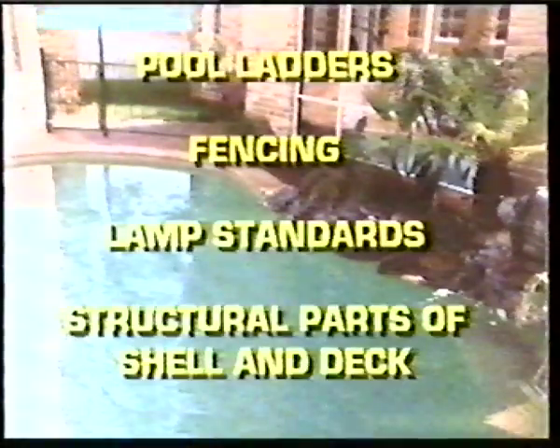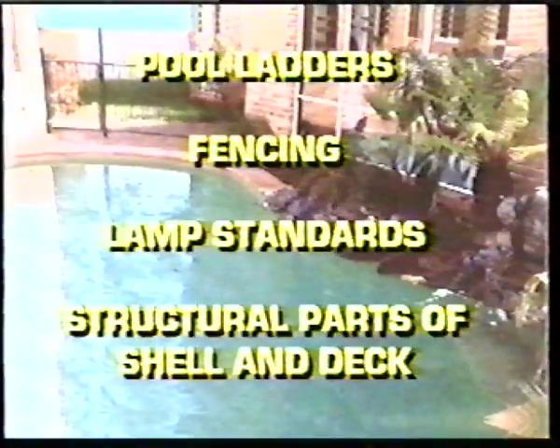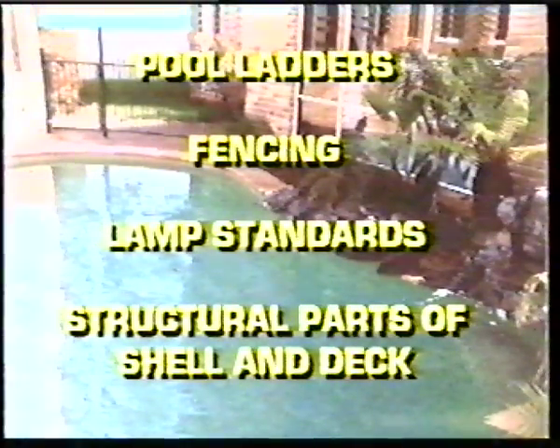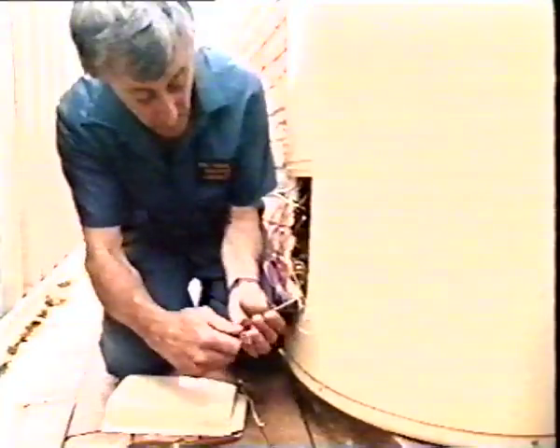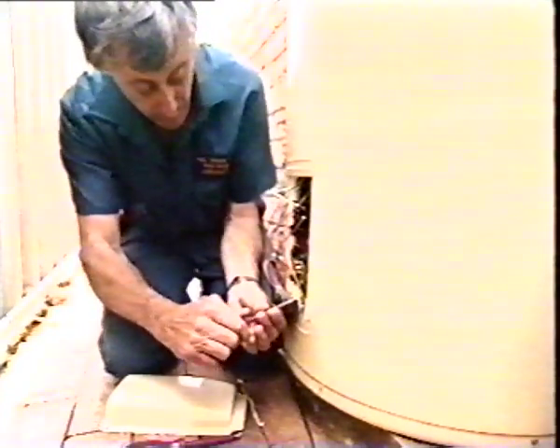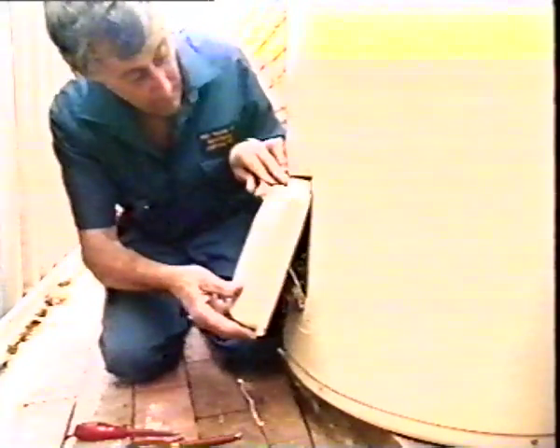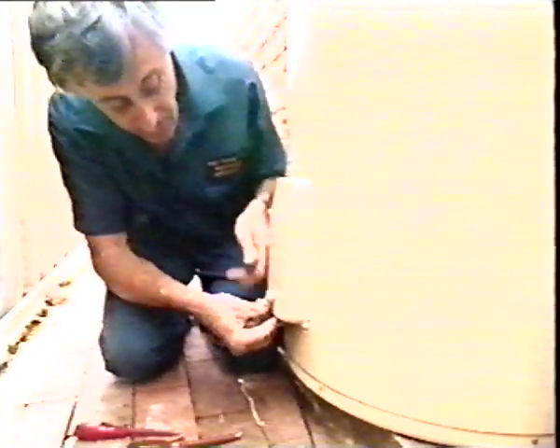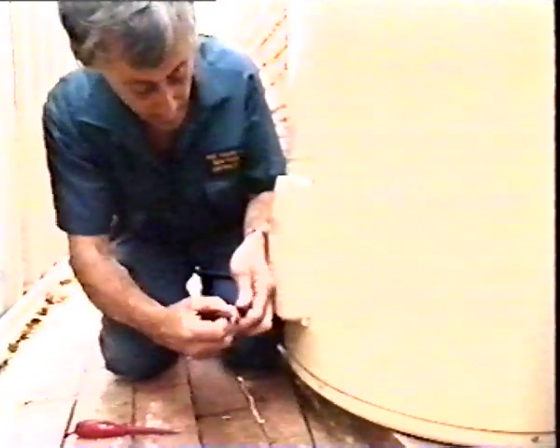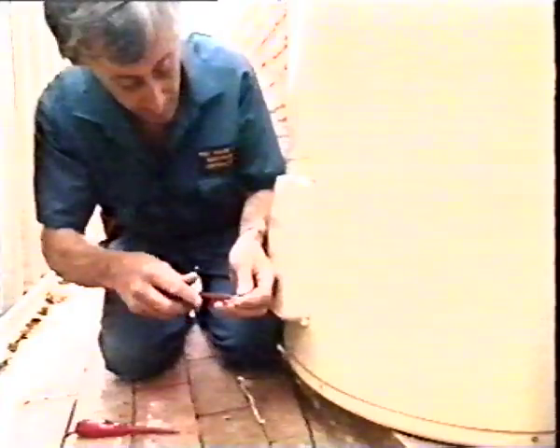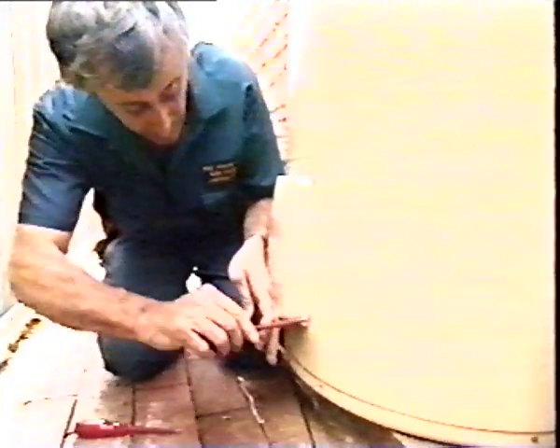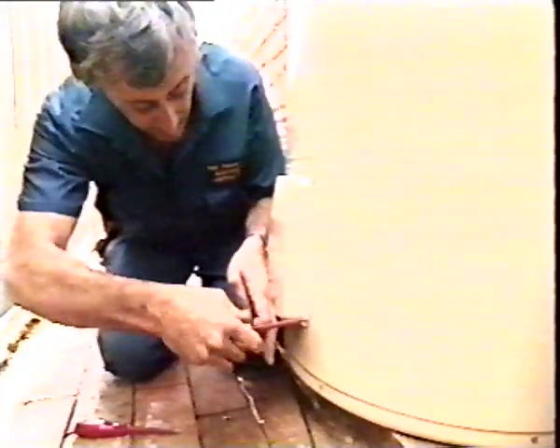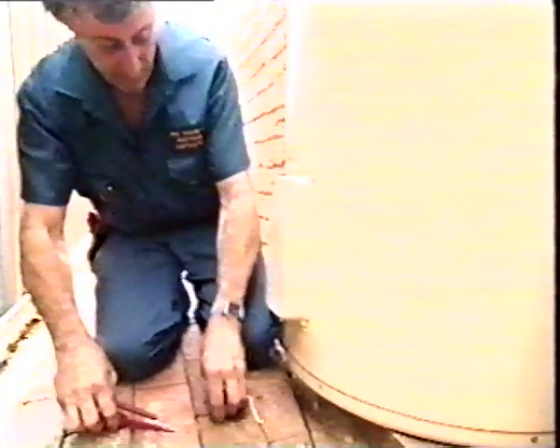Metal swimming pool parts, where they are equipotentially bonded and connected to the earthing system. For instance, pool ladders, fencing, lamp standards and structural parts of the shell and the deck. When you finish the test, reconnect the earthing conductor at the water heater and the main earthing conductor to the MEN connection. That is, unless you're proceeding to test the insulation resistance as in Test B. Don't forget to deduct the resistance of the leads before recording the results.